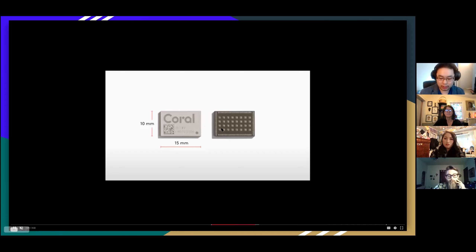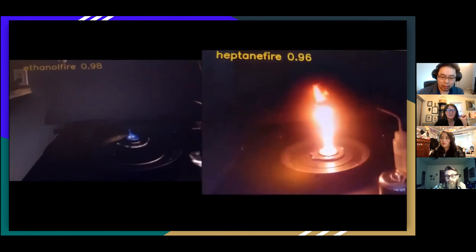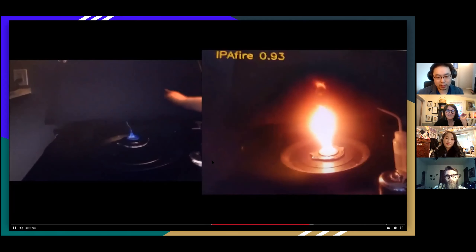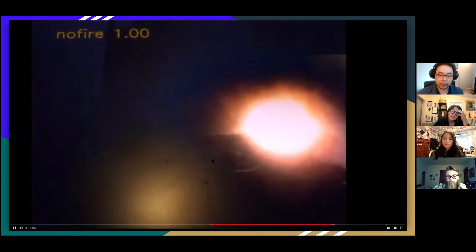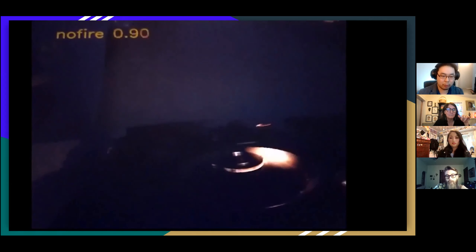In the demo itself, you can see that it correctly identifies the heptane fire. Here again it correctly identifies — the first one is an ethanol fire, the second one is a heptane fire, which is quite vigorous and more or less amorphous. On the left you can see that the ethanol fire, while quite static, has a very difficult time being detected when perturbed. Here we can demonstrate that we can shine a bright light directly at the device, so it's not detecting just bright yellow lights. We can also move the spotlight around in a way that emulates a fire — and again, no false alarm.